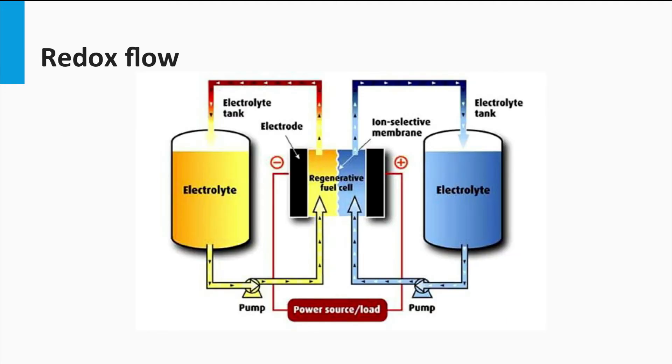The last and most upcoming category is that of the redox flow batteries. The two main storage options for PV storage — lead-acid and lithium-ion batteries — are similar in the sense that their electrodes undergo chemical conversion during charging and discharging. Therefore, the electrodes tend to degenerate with time, adding to the inevitable aging of the battery. Redox flow batteries are a very new technology which seem to combine the properties of both batteries and fuel cells. The different reactants only exchange ions in the form of electrolytes through a membrane in a cell, so the cell reactions proceed without physical mixing of the reactants. The chemical energy is stored in two electrolytes which can be maintained physically separate, giving redox flow batteries a high life expectancy.